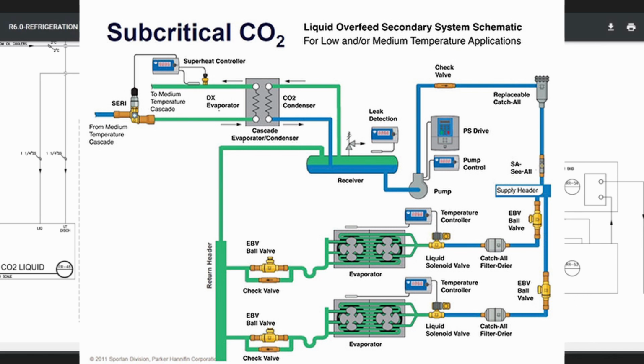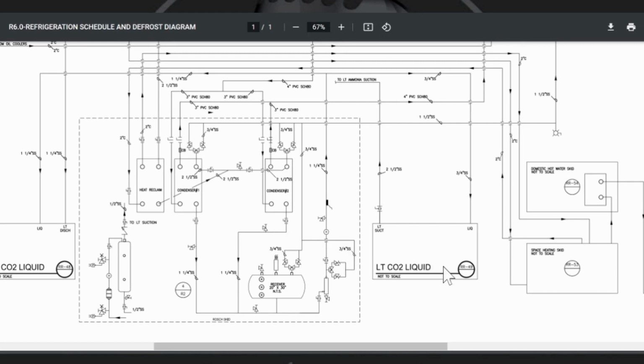Well, no, wait a minute. The tank is not called a thermal siphon. That is just a tank. And above it are mounted, on the medium temp, 4 plate heat exchangers, and they are the CO2 condensers or thermal siphon condensers. So the liquid comes back into the tank, and the plate heat exchangers are colder than the tank, obviously, and therefore the vapor goes up the pipe, condenses on the plates, and drops back down into the tank. And that's a real inefficiency on this system, and we would not build another one like that.